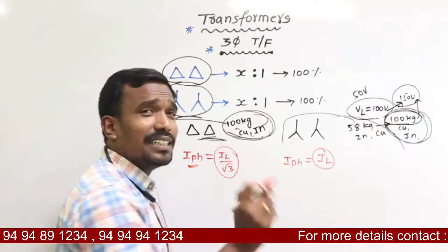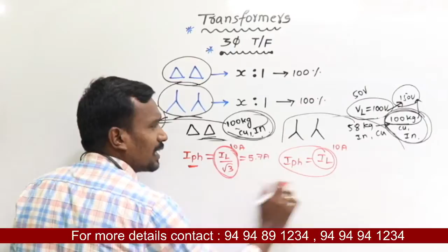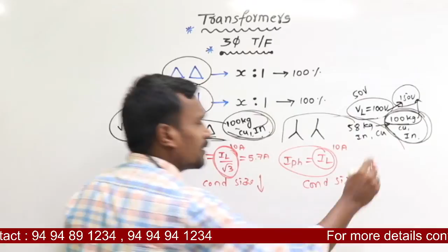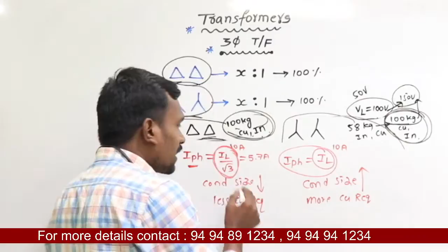For example, if my line current is 10 ampere, here phase current is also 10 ampere. For example, 10 by root 3 is 5.77 amperes. Here less current, here more current. Here conductor size is less, here conductor size is more. More conductor size means less copper required here, and more copper required here because of conductor size. Here conductor size is less.